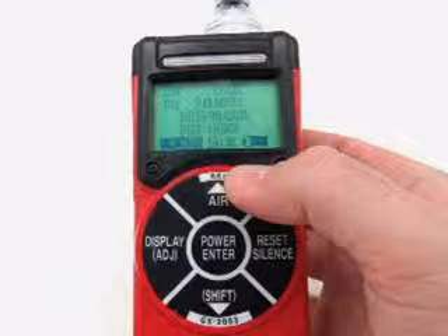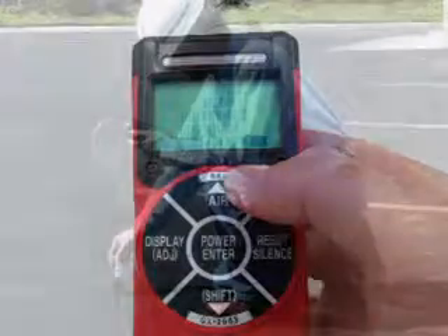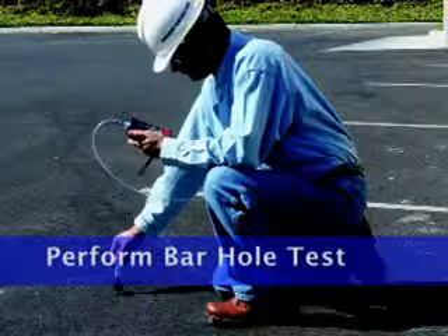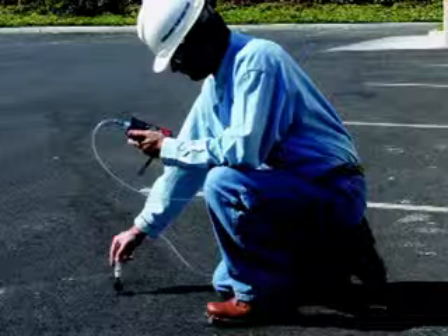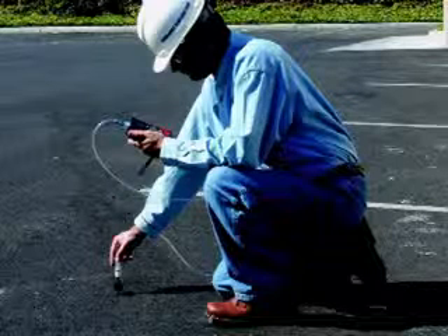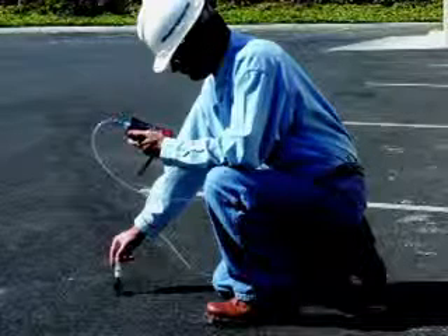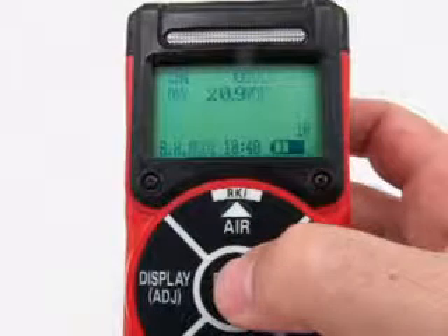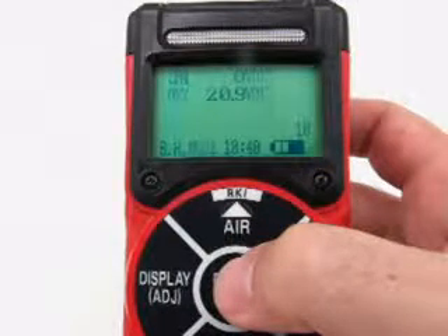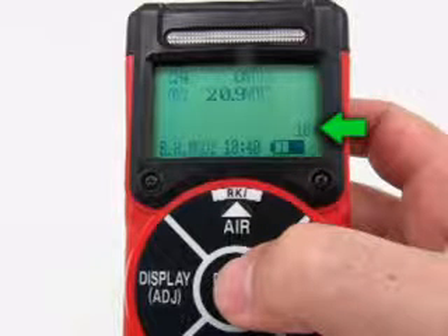At the end of the sample period, the pump will shut off and the peak methane and minimum oxygen levels monitored during the sample period will be displayed. Take the GX2003 to the bar hole that will be tested. Insert the probe into the bar hole and press and release the power enter button. The pump will turn on and the sample period will begin, with the sample period counting down in seconds in the lower right corner of the display above the battery icon.